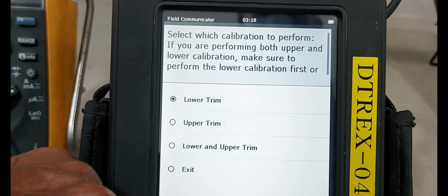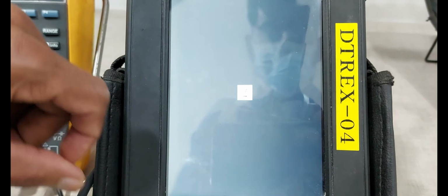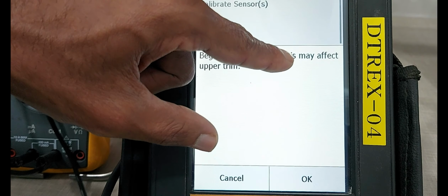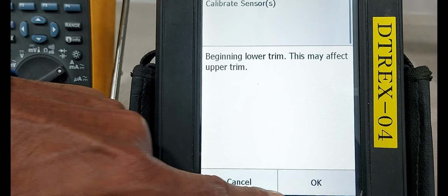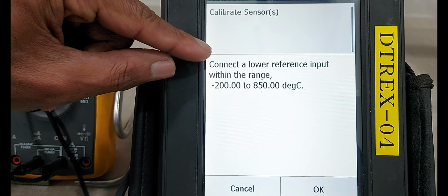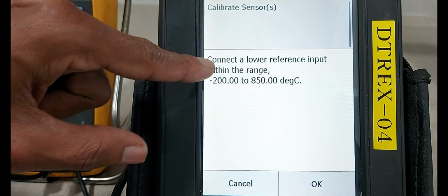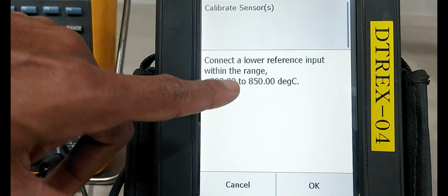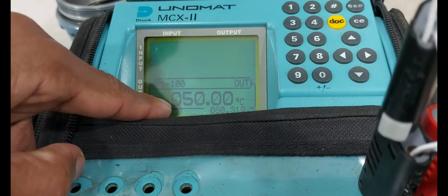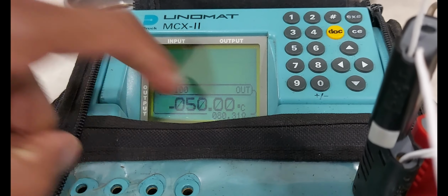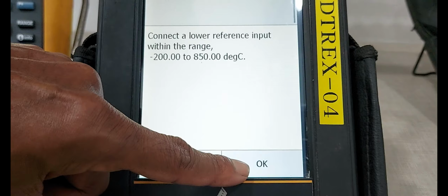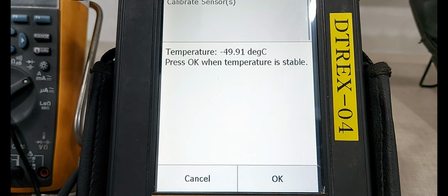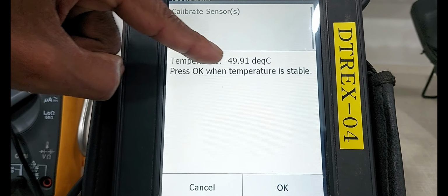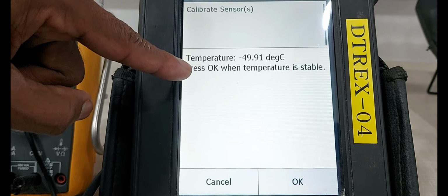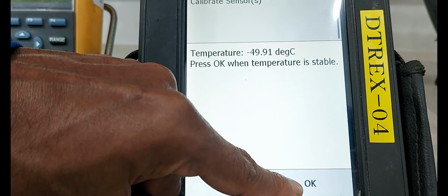Select the lower sensor trim, then okay. Okay, beginning the lower sensor trim, this may affect the upper sensor trim, okay. Connect the lower sensor reference input with the range. Reference temperature -50 degree already set. Then okay. Now temperature showing -49.9 degree. Press OK when temperature is stable. Now temperature is stable. Okay.